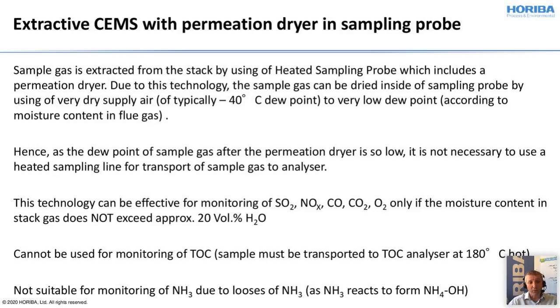If this humidity level is higher, then the permeation dryer is above its limits, and the moisture in the gas behind the dryer might still be present and will bring wrong information or wrong analysis results. Also, it cannot be used for hydrocarbons monitoring with the TOC, because for a TOC analyzer, the analyzer needs to get the sample gas at a temperature of 180 degrees. Otherwise, we have a loss of several hydrocarbons which are exceeding or below this dew point. Also, ammonia monitoring is not possible because of the loss of the ammonia, and the ammonia will react to ammonium hydroxide, also known as ammonia water or ammonia solution.